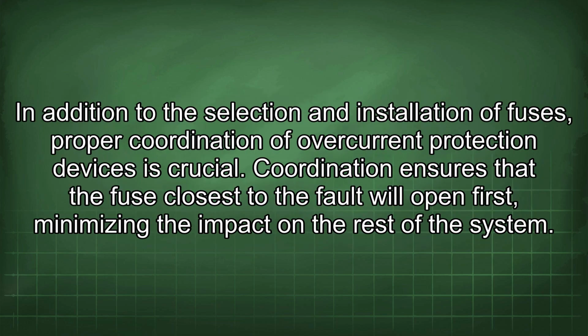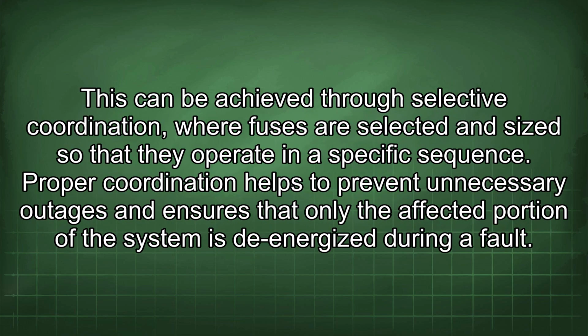system. In addition to the selection and installation of fuses, proper coordination of overcurrent protection devices is crucial. Coordination ensures that the fuse closest to the fault will open first, minimizing the impact on the rest of the system. This can be achieved through selective coordination, where fuses are selected and sized so that they operate in a specific sequence. Proper coordination helps to prevent unnecessary outages and ensures that only the affected portion of the system is de-energized during a fault.